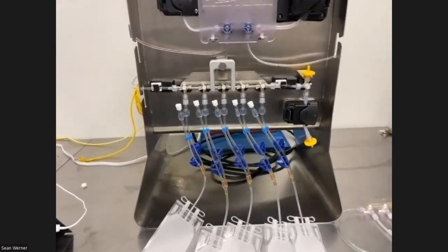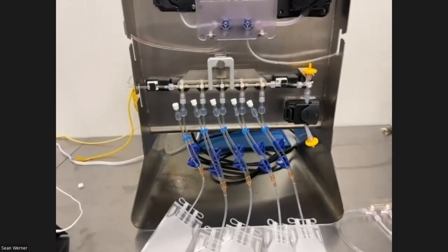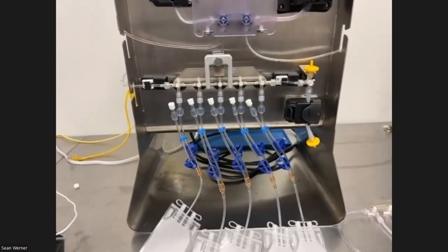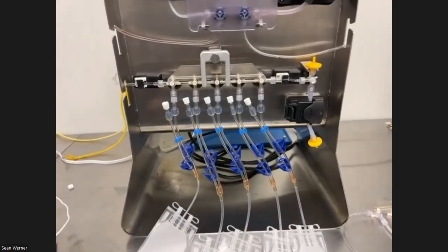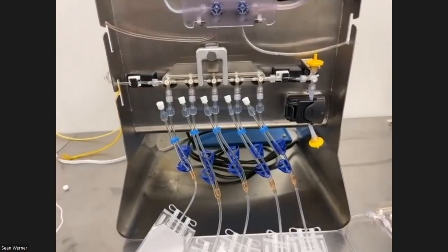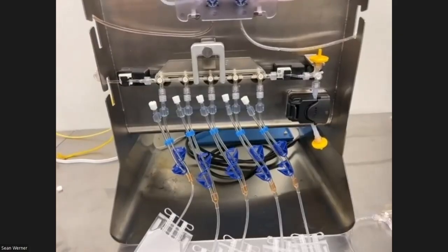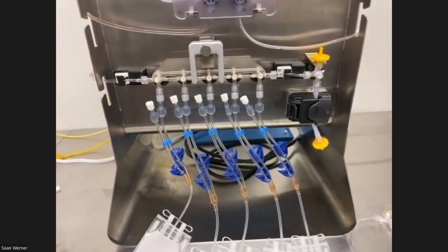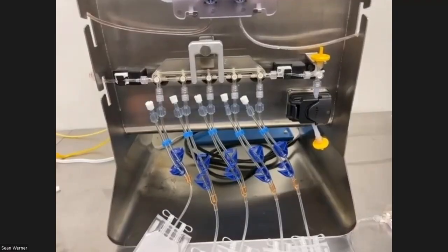Do you have leachables and extractables data for this? What's the percent DMSO and the exposure time for the kit? Amy, do you remember what we have specifically on this? I know off the top of my head, I can't remember exactly what we have in hand on that. The DMSO, obviously with PVC, is potentially an issue, but so far, anything that we know in terms of changing the performance of the tubes, we haven't found any problems. The residence time is pretty low. In terms of extractables, I have to double check and see what data we have. I can't remember what we've collected on this.